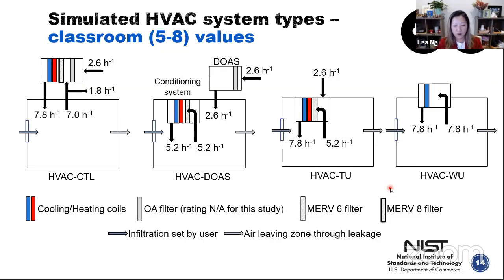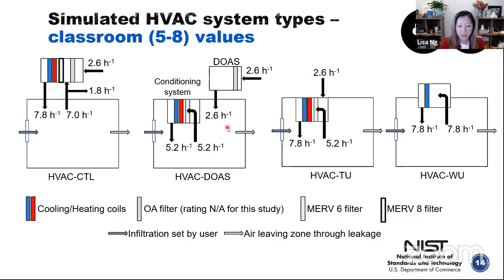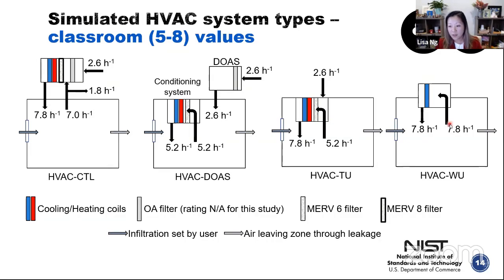We looked at different ventilation types because schools vary widely. CTL is the central system — a pressurized system where supply is greater than return, outdoor air is filtered, and return air is filtered through a MERV 8 filter. The DOAS system is a 100% dedicated outdoor air system; its conditioning unit has a MERV 6 filter. The terminal unit system is like the DOAS system but without dedicated outdoor air — air comes directly into the system and mixes with return air. The window unit system has negligible outdoor air and a negligible rated filter. For the DOAS system, note there are different types — this is an air-driven one; if you have radiative baseboard heaters there may not be this exchange of air.